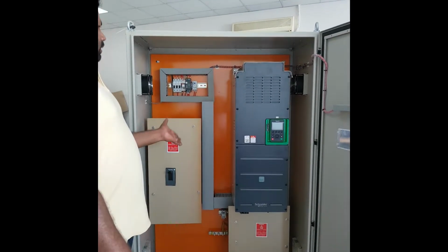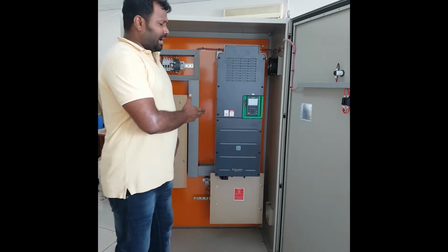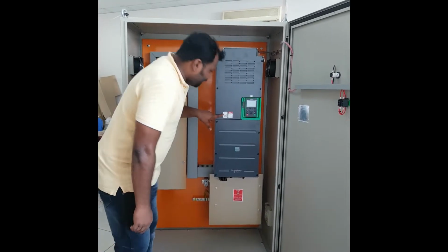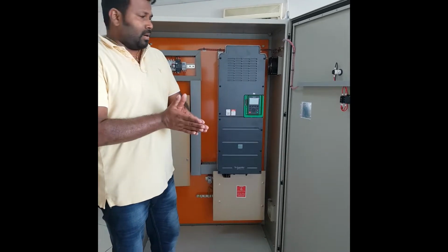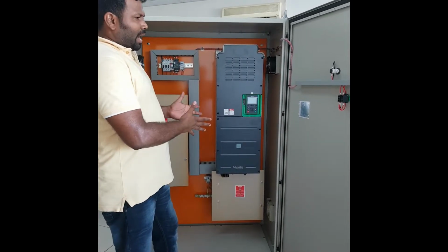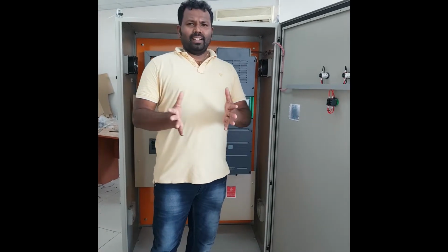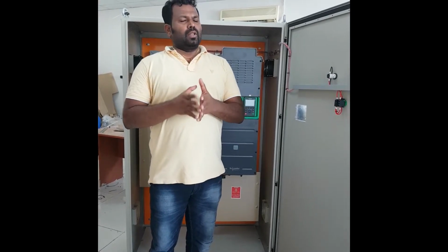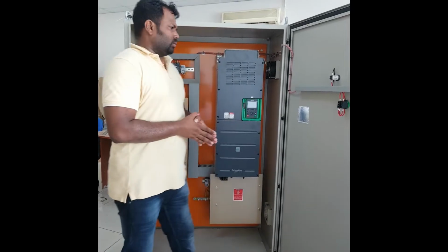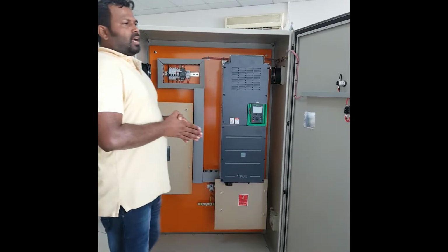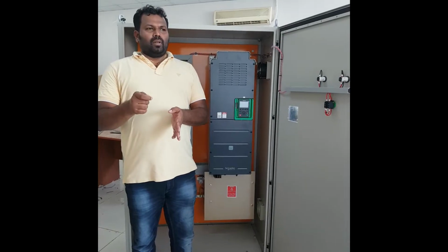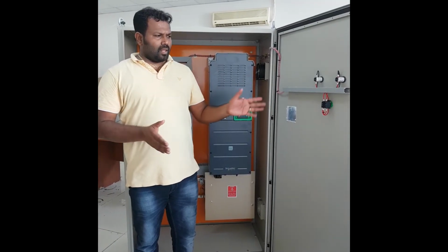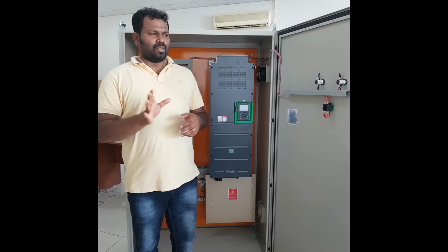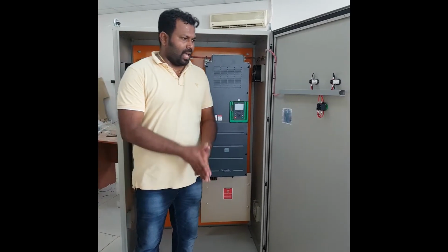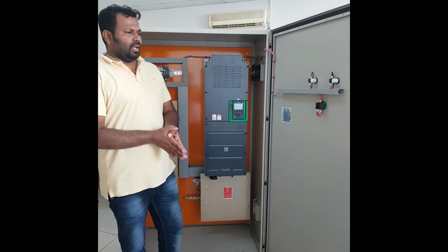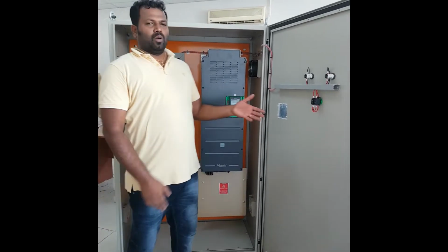So this is the VFD, Schneider brand. The model is ATV 630, a 132 kilowatt VFD for pump application. This panel is a basic design to run a 132 kilowatt borewell pump. The panel has two operation modes: hand mode and auto mode. In hand mode the pump will start directly, and for auto mode we have given a remote provision.